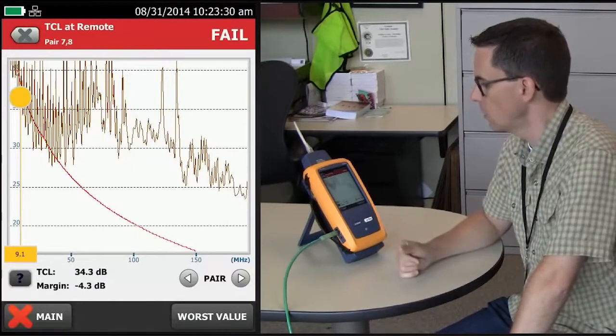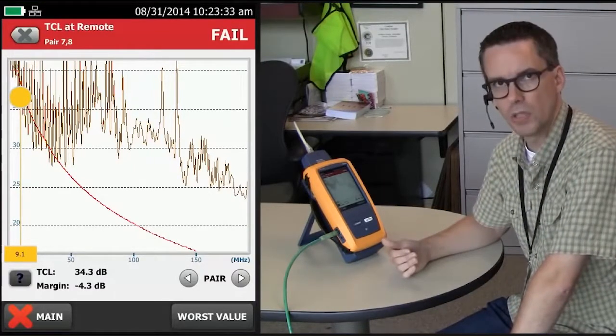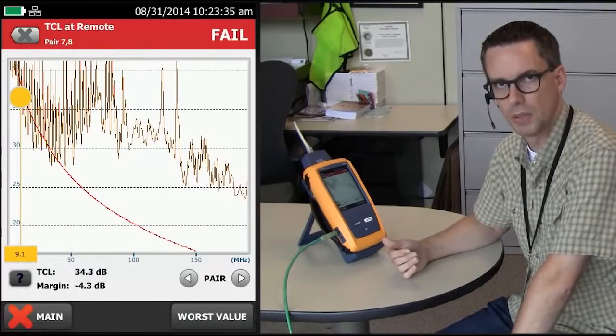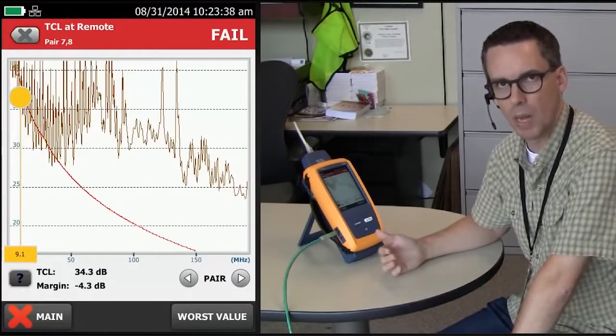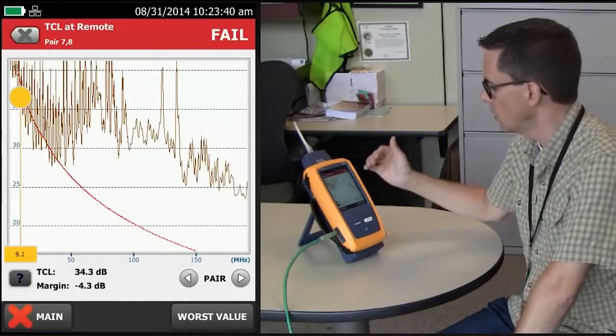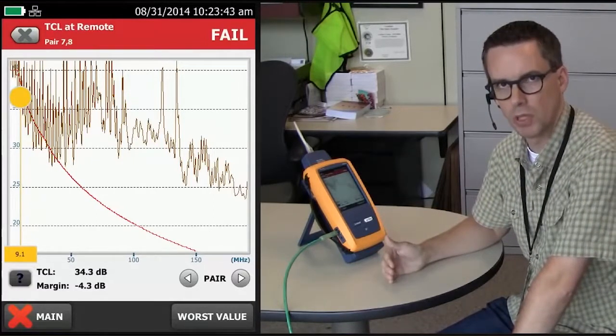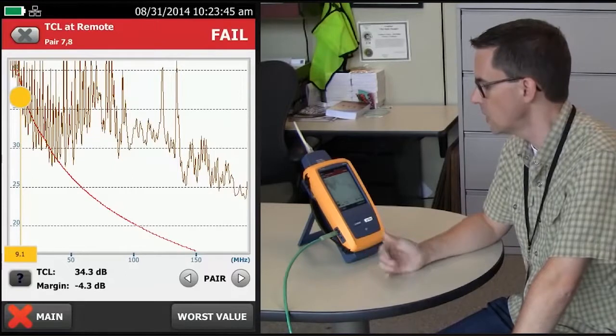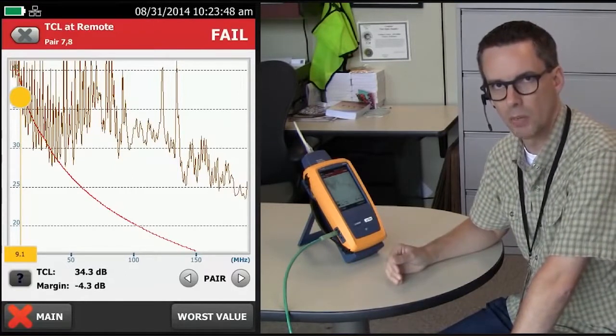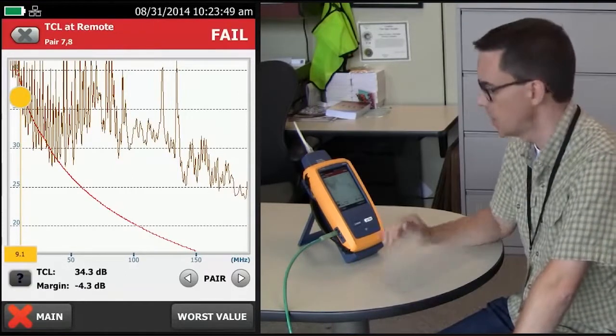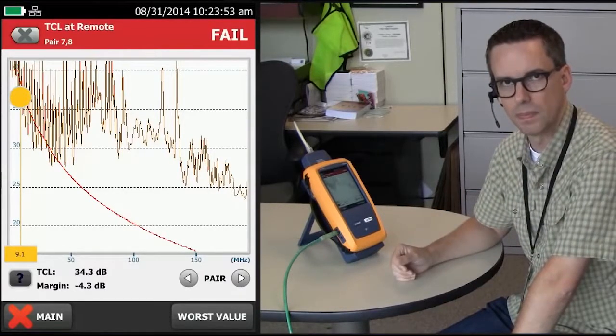So what do we learn from this? You can have great confidence in doing a certification test, but there may be a rare occasion where you have poor balance in the cable. Consider TCL at this stage as a troubleshooting tool. You can't use it as a certification tool because there are no limits for the permanent link — but keep that in mind as a potential future test.